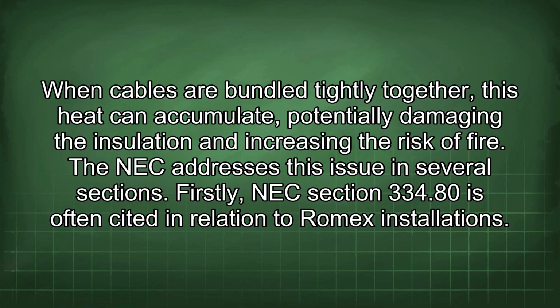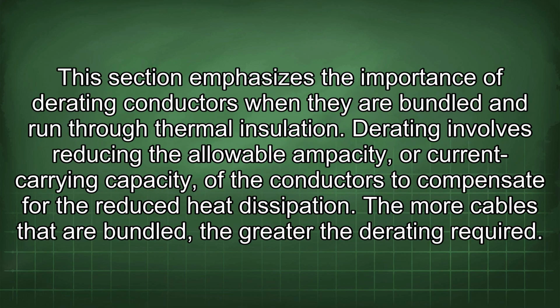Firstly, NEC Section 334.80 is often cited in relation to Romex installations. This section emphasizes the importance of derating conductors when they are bundled and run through thermal insulation. Derating involves reducing the allowable ampacity, or current carrying capacity, of the conductors to compensate for the reduced heat dissipation. The more cables that are bundled, the greater the derating required.